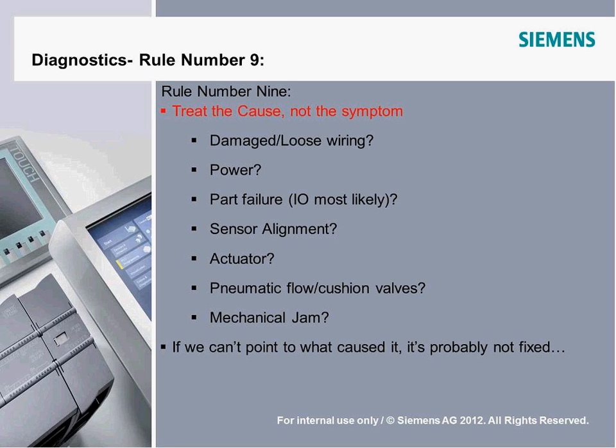Mechanical jams happen all the time, and oftentimes people will blame the control system when it is actually just a bunch of cardboard stuck in a sleeve or something that is not allowing the machine to function.